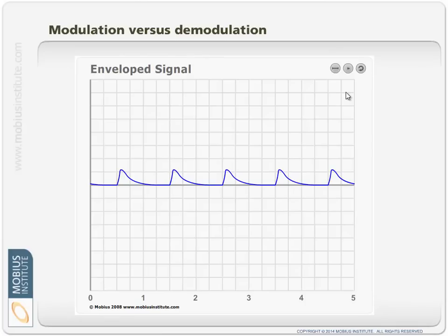But as you can see, we use demodulation in the case of outer race faults on bearings where there was no modulation in the first place. It's a coincidence that we've got modulation in the case of inner race faults, and we use demodulation to analyze it. They're just two different processes altogether. But what I would tell you is that we can use that process even for gear faults and broken rotor bars as well. Again, nothing to do with the fact that they actually cause modulation. It's because as those gears impact each other, if they were a bit worn or there was a crack or whatever, they also create this high frequency vibration.